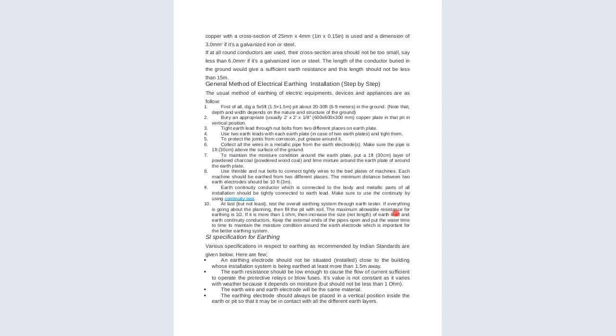The maximum allowable resistance for earthing is 1 ohm. If it is more than 1 ohm, then increase the size or length of the earth lead and earth continuity conductors. So keep the external ends of the pipes open and put water in from time to time to maintain the moisture condition around the earth electrode, which is important for a better earthing system.